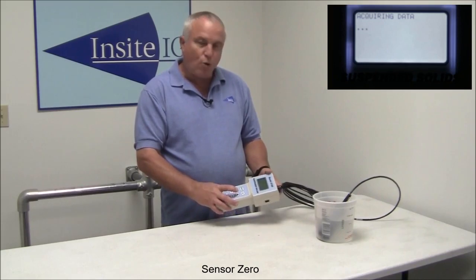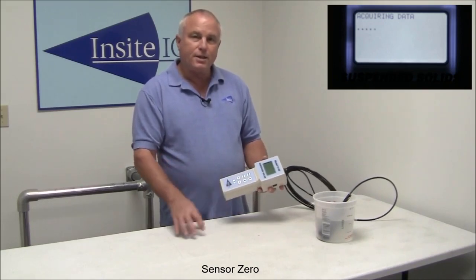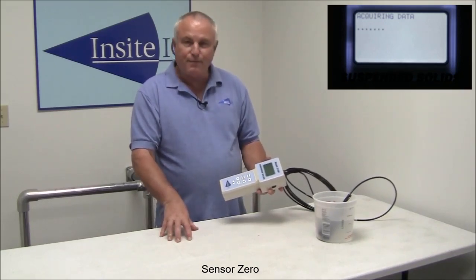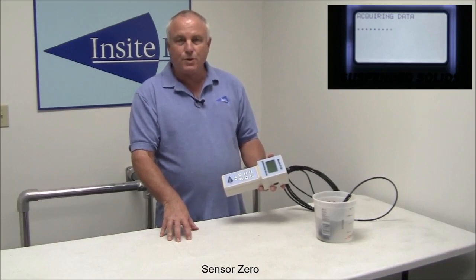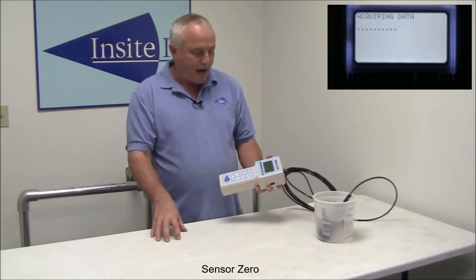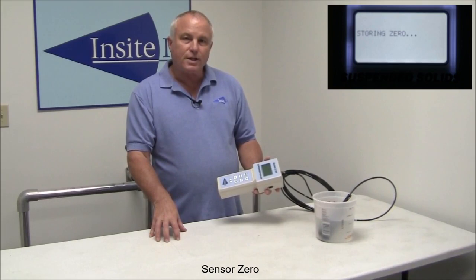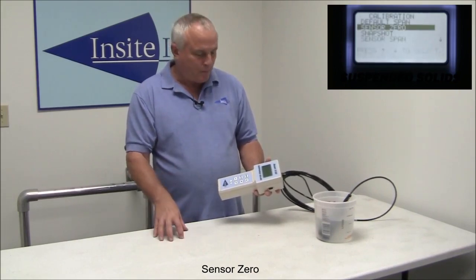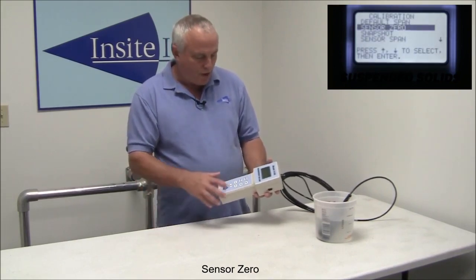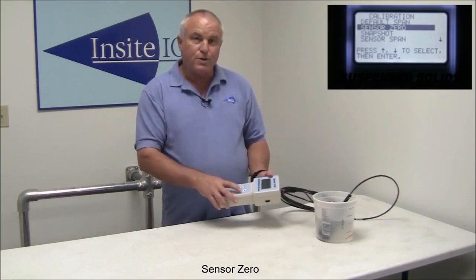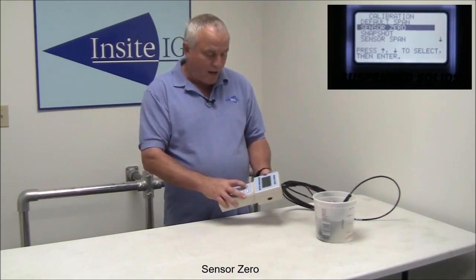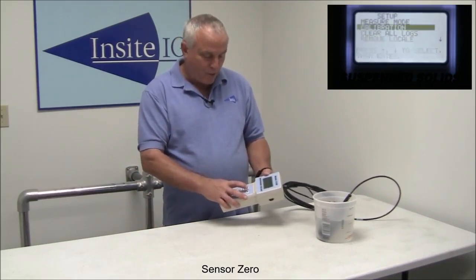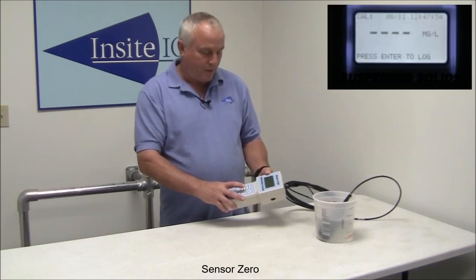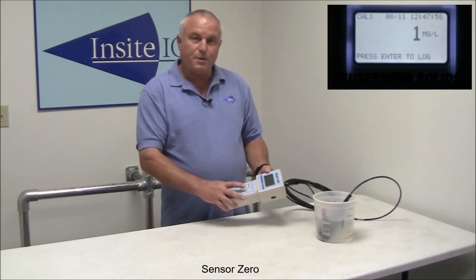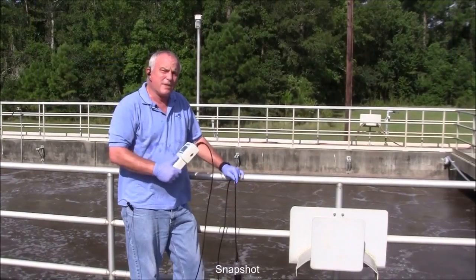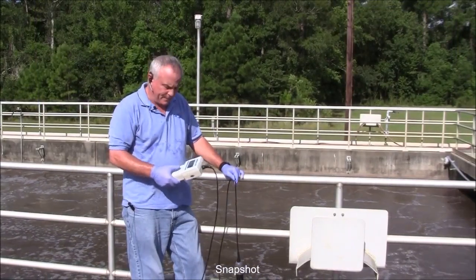It's going to come up and say acquiring data. And this is going to take approximately 15 seconds. What it's doing is it's taking a whole bunch of samples and then averaging them together so you get nice clean signal. So it's stored to zero. That's all there is to do in the zero. Now we just menu our way out, back to the run mode, press enter. It comes up zero.